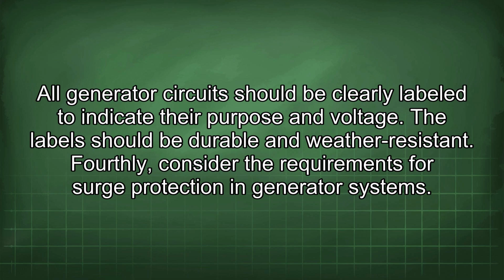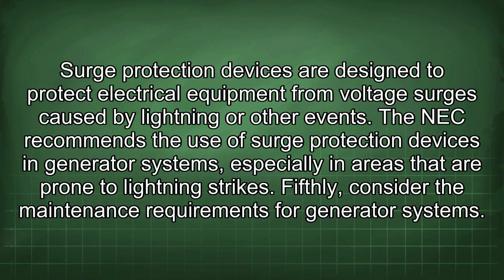All generator circuits should be clearly labeled to indicate their purpose and voltage. The labels should be durable and weather resistant. Fourthly, consider the requirements for surge protection in generator systems. Surge protection devices are designed to protect electrical equipment from voltage surges caused by lightning or other events. The NEC recommends the use of surge protection devices in generator systems, especially in areas that are prone to lightning strikes.